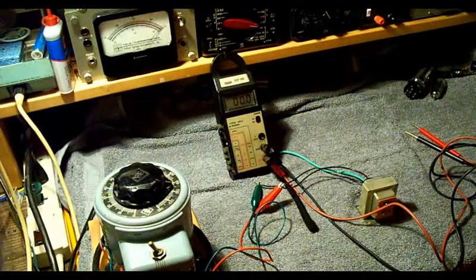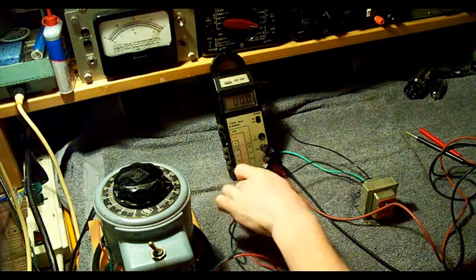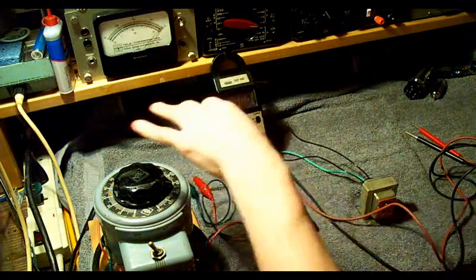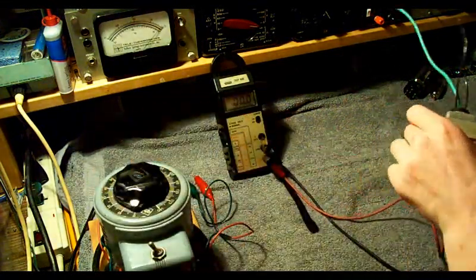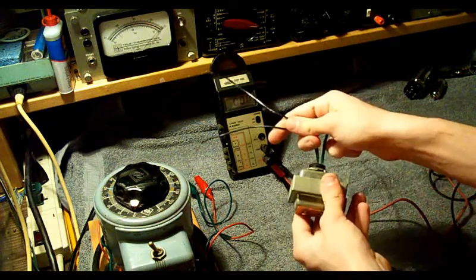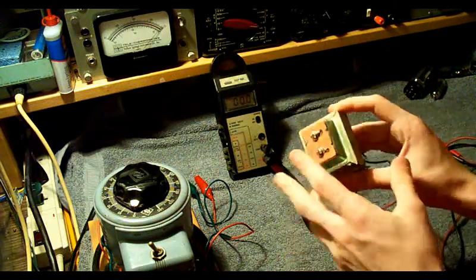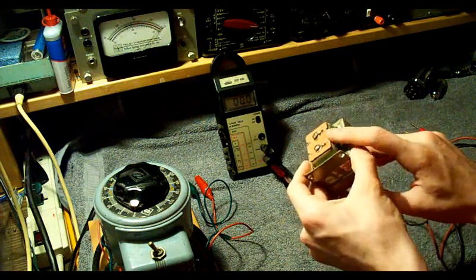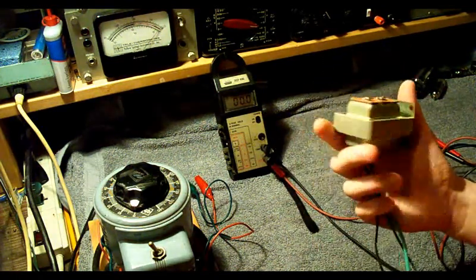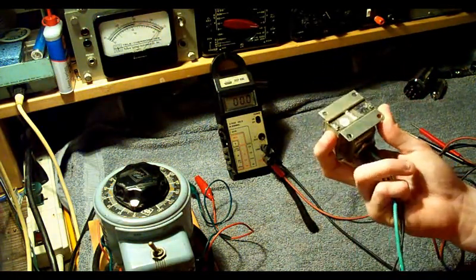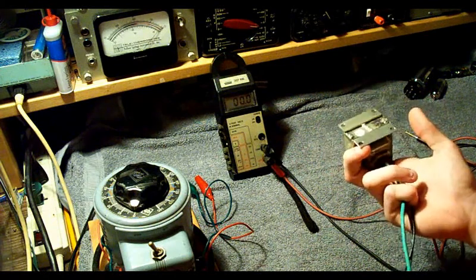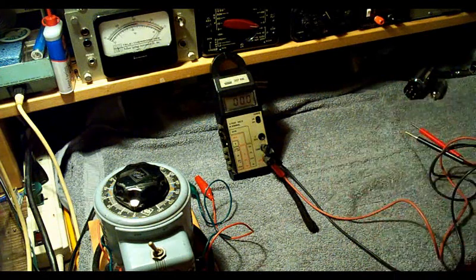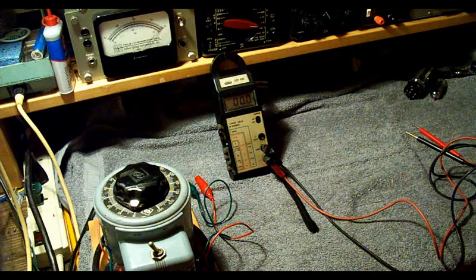So clearly, something is wrong with this transformer, that we are getting 120 volts coming out of the secondary winding. That is not supposed to happen under any circumstances. So we now have proven that this transformer is defective. We input 120 volts on one side, we get 120 on the output. We should not be getting that. We should be getting anywhere from 10 to about 15 volts AC, and when it's unloaded it might climb to as high as 20 volts. So this is a bad transformer.